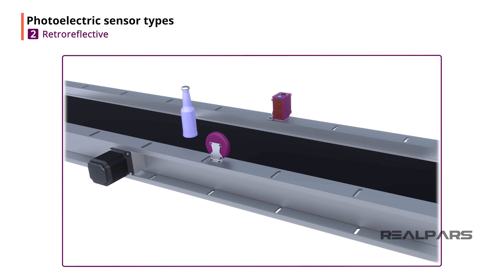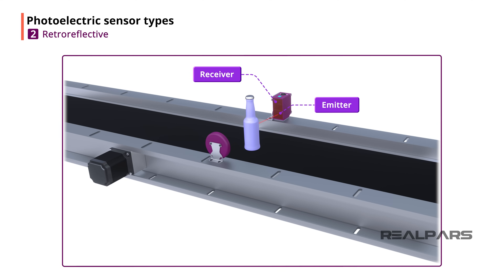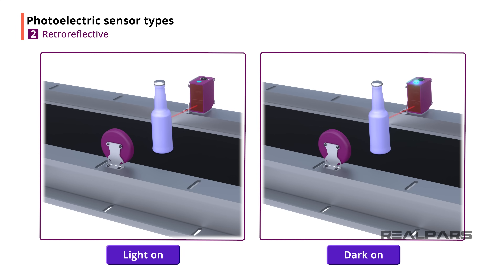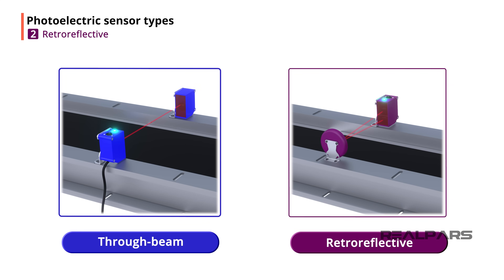Retro-reflective photoelectric sensors have the emitter and receiver together in the same component. For the retro-reflective sensor to work, the sensor's emitter needs to be pointed at a reflector and aligned, so the light travels from the sensor's emitter to the reflector and then bounces back to the sensor's receiver. The retro-reflective sensor output works the same as the through-beam sensor output: the output is on if the light is not blocked, and off if the light is blocked. Retro-reflective sensors can also have a light on/dark on mode selector switch. Retro-reflective sensors have a shorter detection range compared to through-beam sensors, because the light has to travel to a reflector and then back to the sensor, instead of just traveling straight to the receiver.